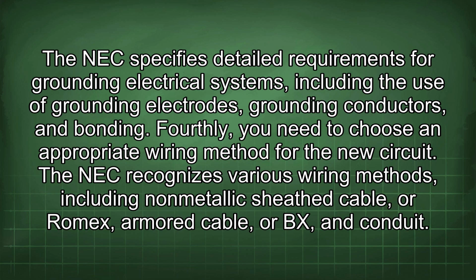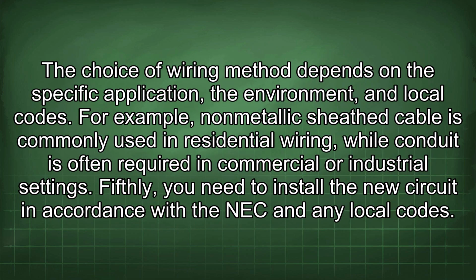Fourthly, you need to choose an appropriate wiring method for the new circuit. The NEC recognizes various wiring methods, including non-metallic sheath cable, or Romex, armored cable, or BX, and conduit. The choice of wiring method depends on the specific application, the environment, and local codes. For example, non-metallic sheath cable is commonly used in residential wiring, while conduit is often required in commercial or industrial settings.